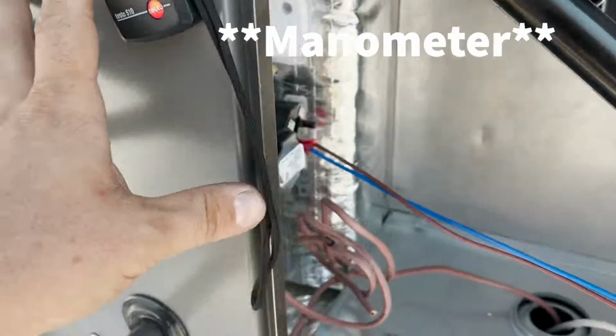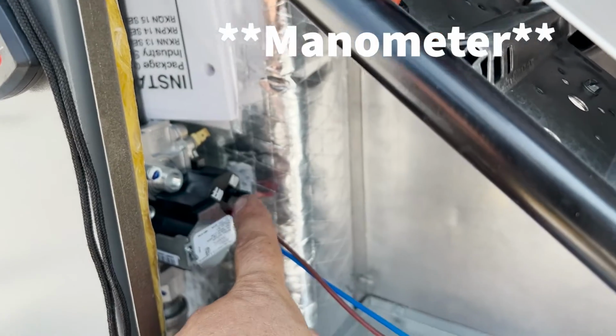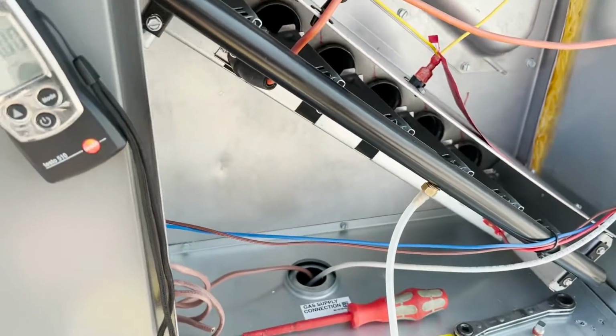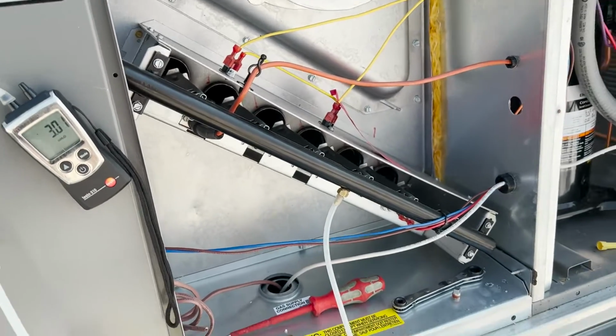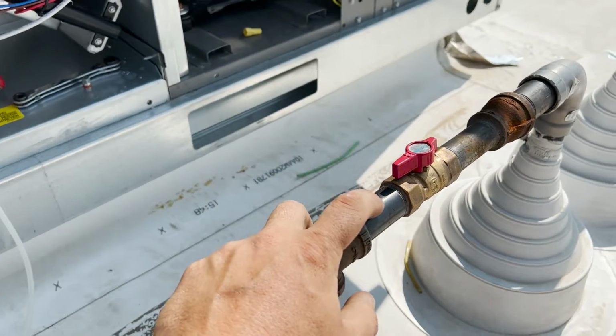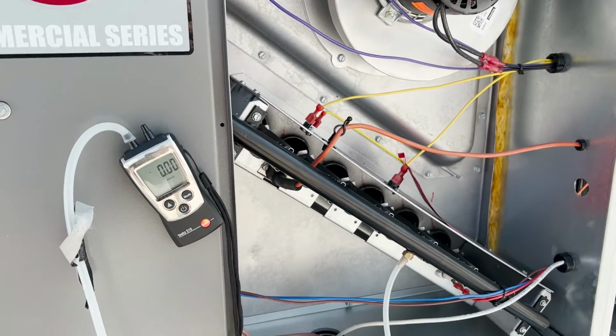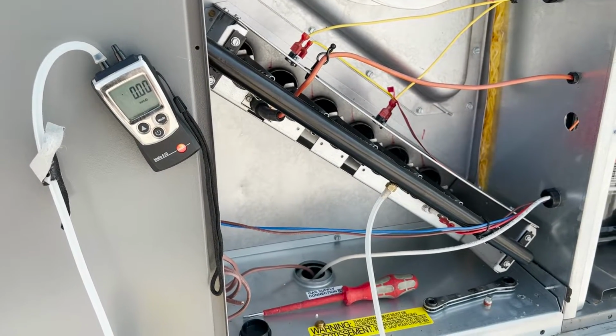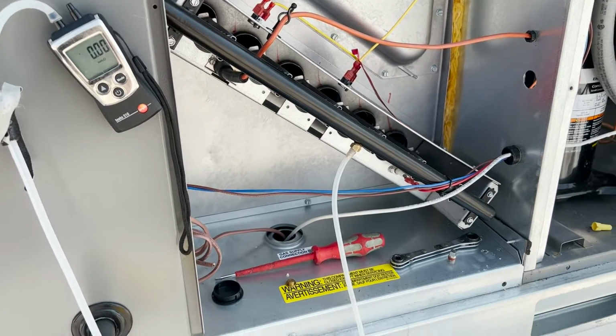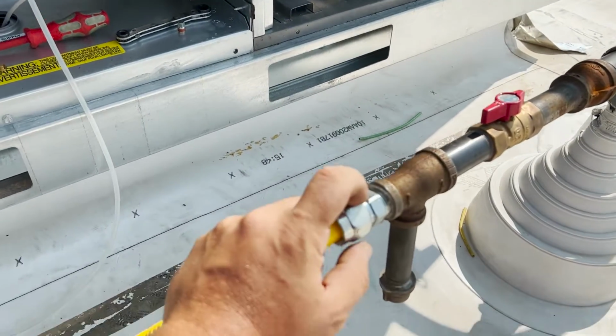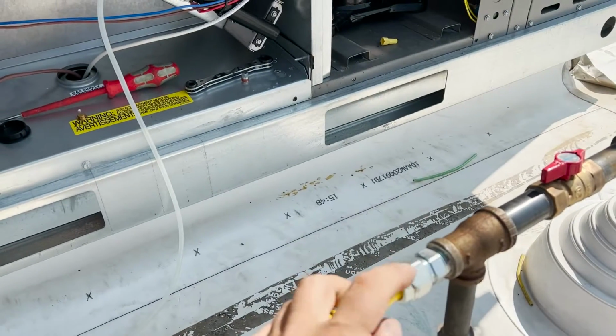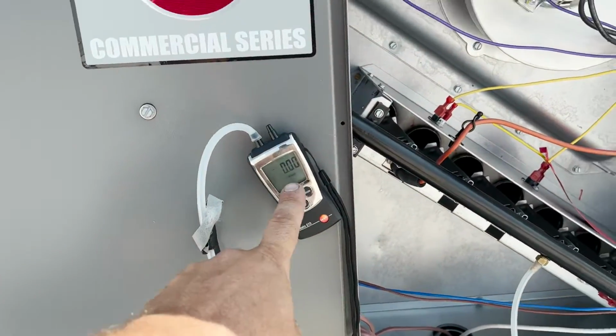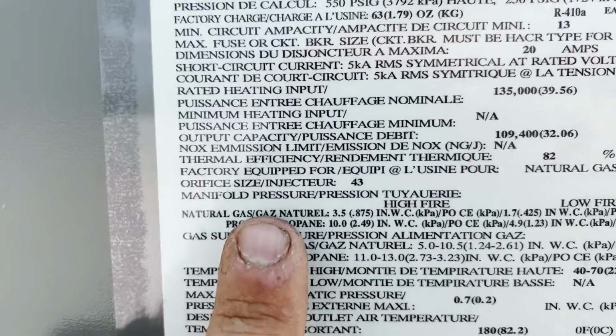Make sure our scale's zeroed. Make sure that our gas valve is on. Now it's very possible on these new construction lines that this needs to be purged of all the air in the line. But we're not going to walk away from this until we know our gas pressure is set right. So if we need to get a couple wrenches and break this open to purge it, we'll do that. But we're going to make sure that we get good flow and set our gas pressure to what's required of us, which on this unit is 3.5, if I can find it. Right here, boom, natural gas, 3.5 inches of water column.